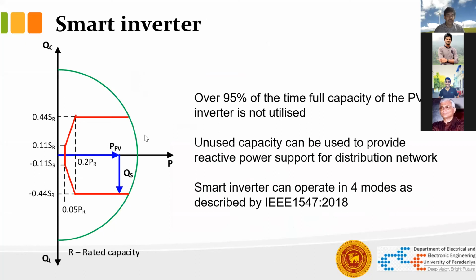Now, this is what is requested by the IEEE 1547 from a smart inverter. As you can see, when the P is 0, you can use the entire capacity of the inverter for reactive power compensation. However, the IEEE 1547 doesn't ask for that. It asks that from 5% of the rated power, you are supposed to give plus or minus 11% of the rated value of reactive power. Then it linearly increases up to 20% of PR. Then you are supposed to give 44% of the capability of your inverter as reactive power.